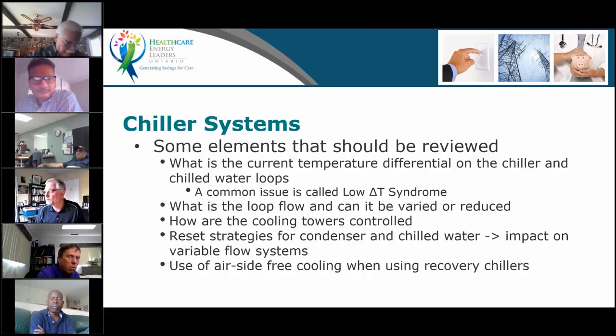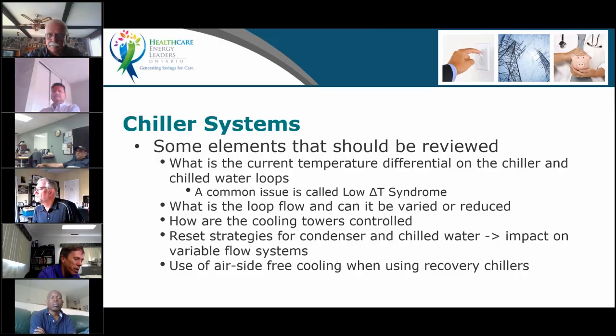If they're very low, depending on the load, obviously, it is a sign that it may be over pumping. You may have other issues. There's like 10 different possibilities when you have a load, and I say 10, there's a large number of possibilities. Could be a dirty coil, could be a number of things, but look at the flow. That's an easy one to look at. Also check, is the loop flow, can it be varied? Can I go variable flow?